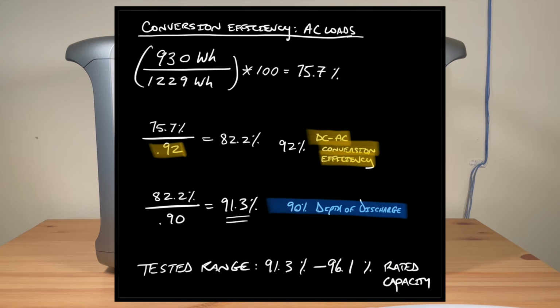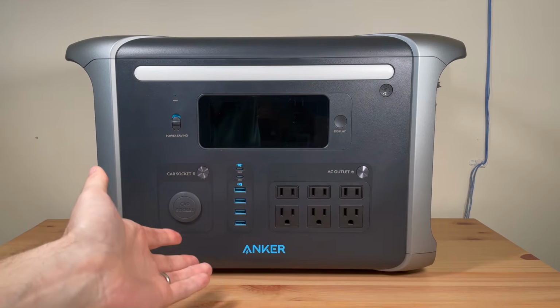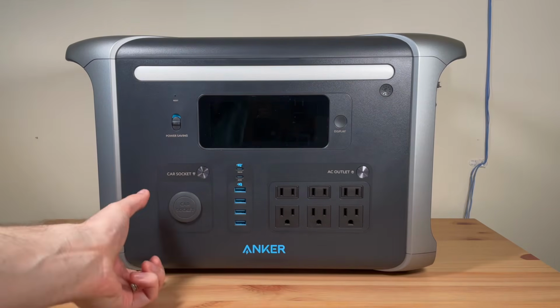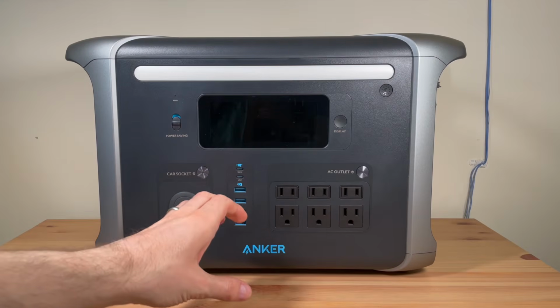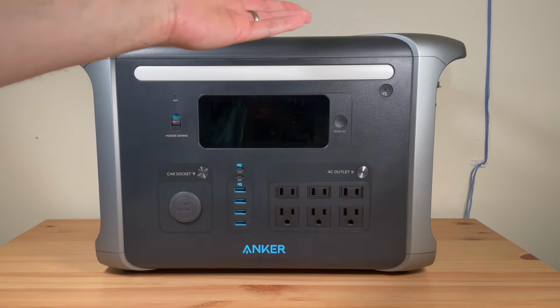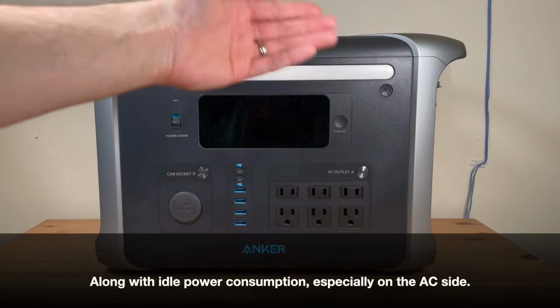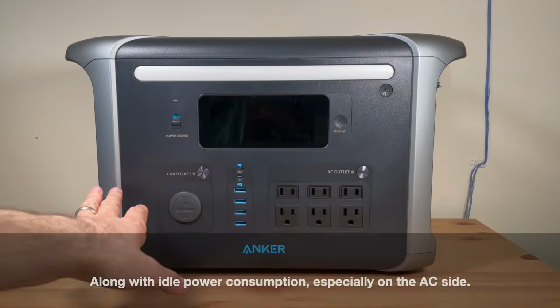I feel fine about what they've stated the capacity at compared to what you get out of it when you use it. But the TLDR of all this: keep in mind, just like any other battery pack, this is effectively a 1 kilowatt hour pack. It is not a 1.229 kilowatt hour pack, because 10% of that goes to reserve capacity in the battery, and there are losses in the DC to AC conversion. That's why you always want to use DC whenever you can.